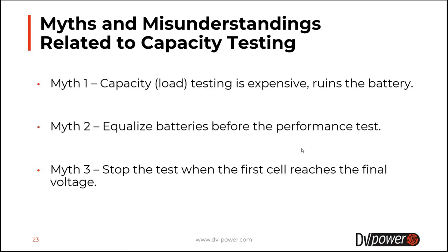It is a crucial thing to be aware of, because you cannot allow the mistake to happen, because those mistakes are too often expensive and have big consequences. Without capacity test, the mistake is inevitable, and you simply cannot know whether the battery is good enough for another year or years of service or not. Also, it is a myth that the capacity test ruins the battery, because batteries are manufactured for a few hundred cycles of charging and discharging, and one of those cycles every year does not mean much compared to those few hundred.